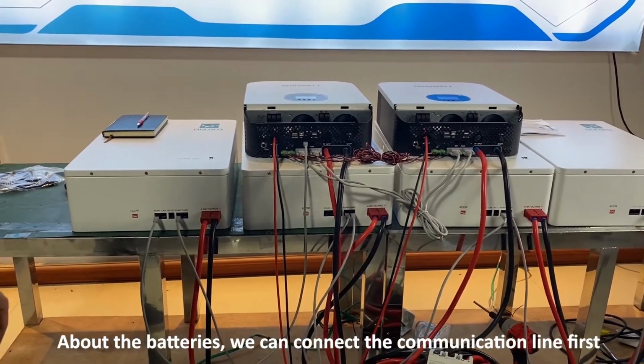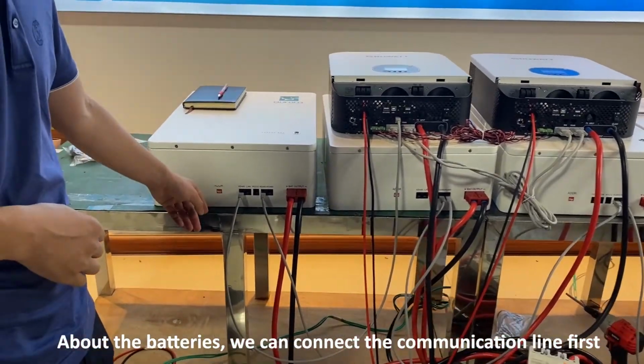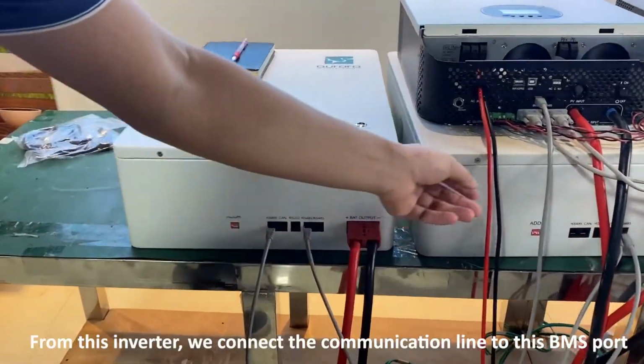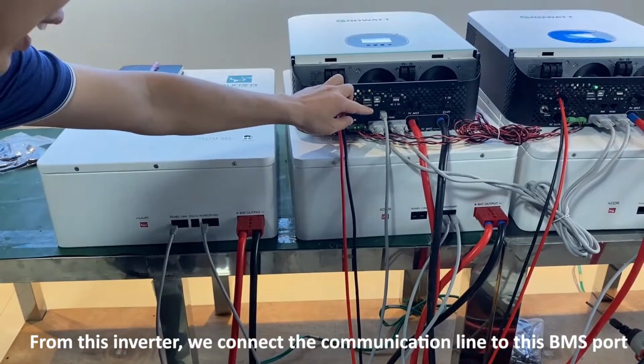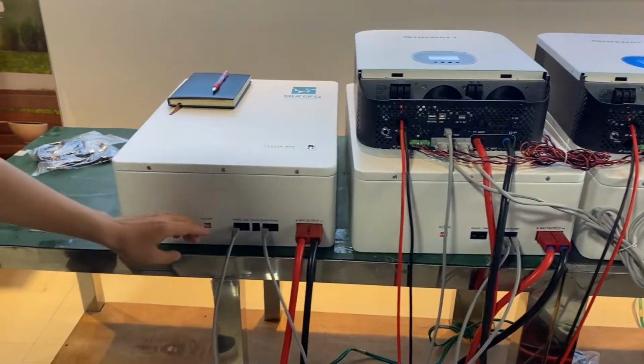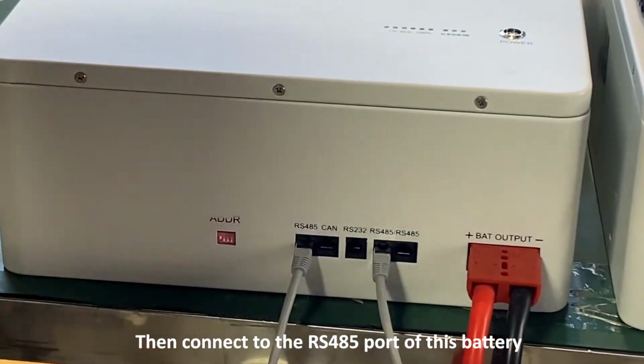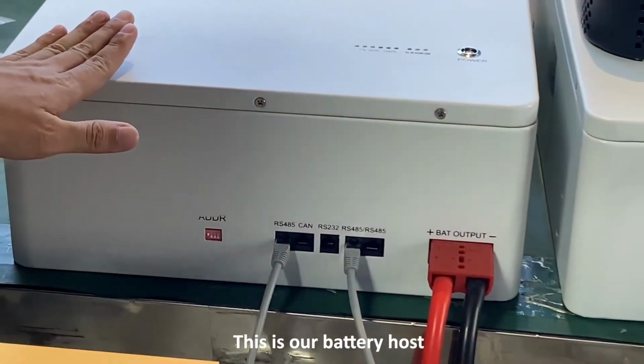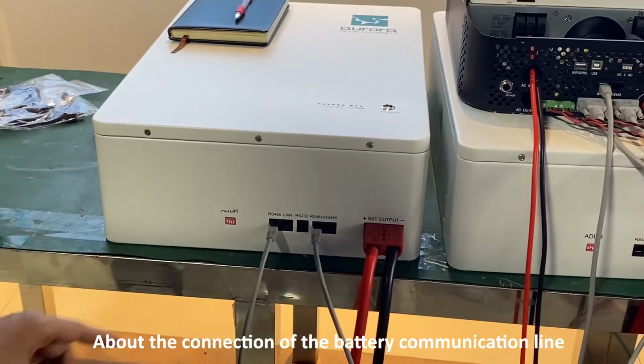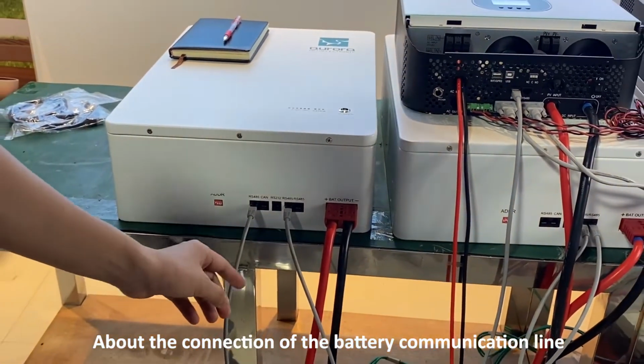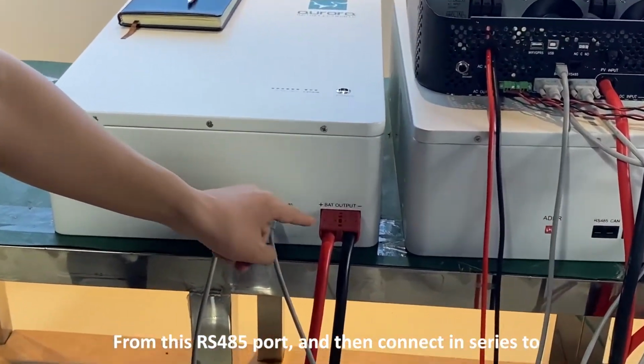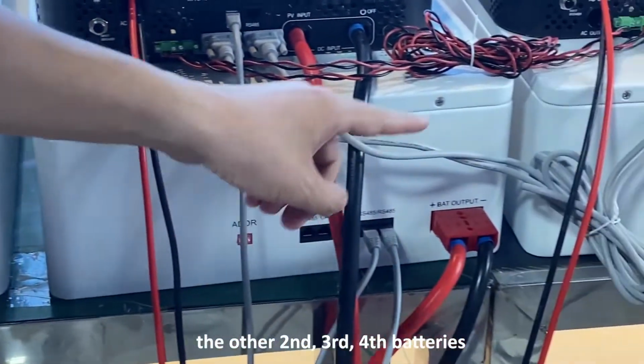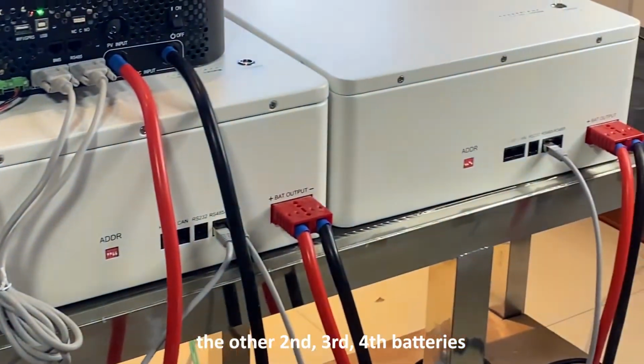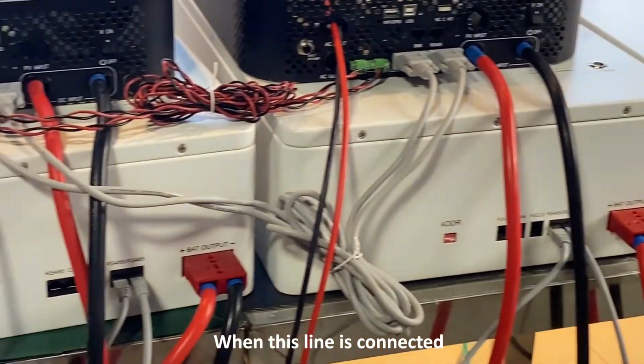About the batteries, we can connect the communication line first. From this inverter, we connect the communication line to this BMS port. Then connect to the RS485 port of this battery. This is our battery host. From this RS485 port, the battery communication line is connected in series to the second, third, fourth batteries.